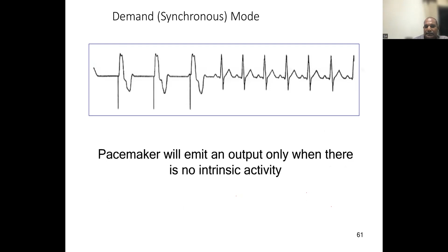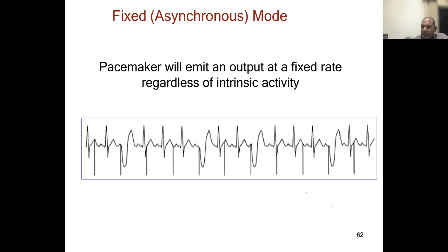So yeah, here what happens is the patient has an adequate rhythm, and at the same time, the pacemaker is also competing with the rhythm and trying to pace. This is because we have used an inappropriate pacing mode here. While the patient has intrinsic activity, the pacemaker is also trying to pace because the pacemaker can't see what's happening. So here the sensing activity is being taken out. So the pacemaker is in an asynchronous mode. That's why asynchronous mode can be dangerous in some situations.